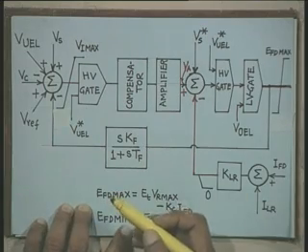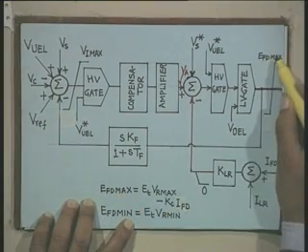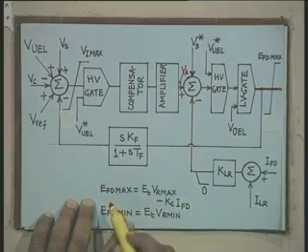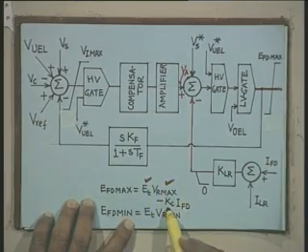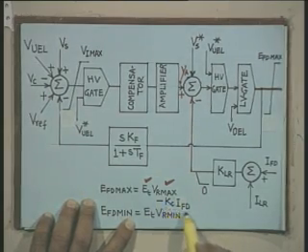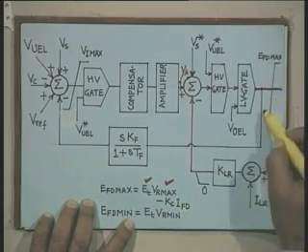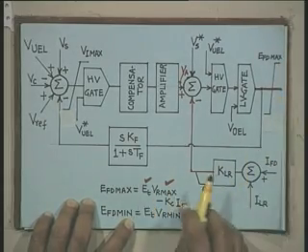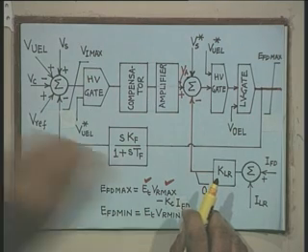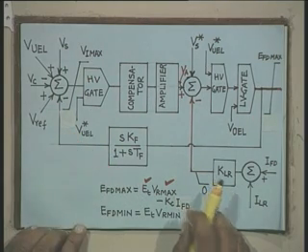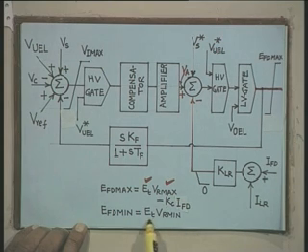Now, here this EFD max is a function of terminal voltage ET, VR max, and KC, the constant depending upon the commutating reactance, and IFD. This maximum voltage is a function of terminal voltage, because the potential transformer takes its input from the terminal voltage itself, and the minimum is ET into VR minimum.